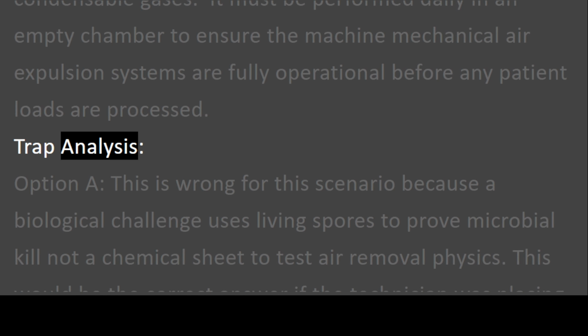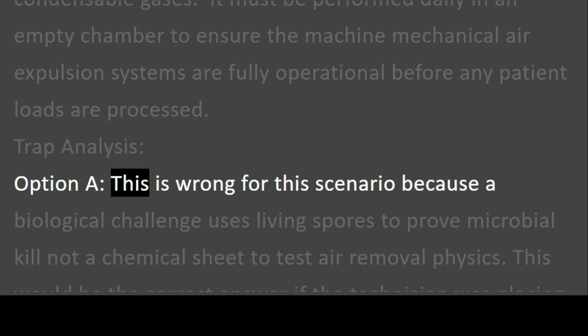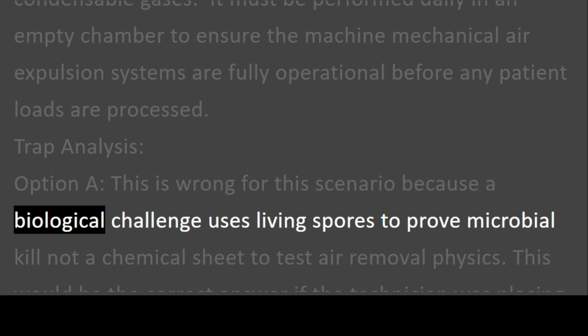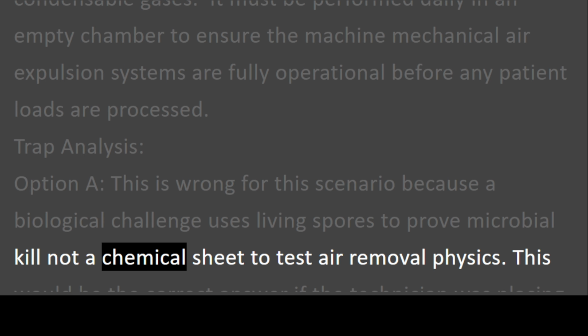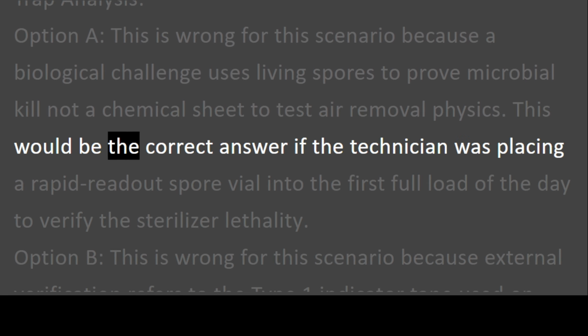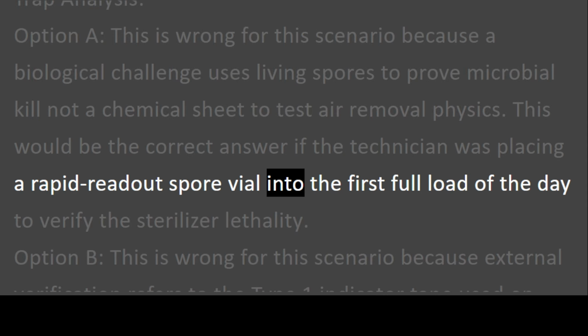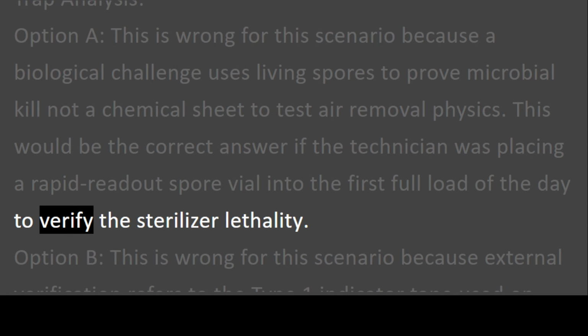Trap analysis. Option A. This is wrong for this scenario because a biological challenge uses living spores to prove microbial kill, not a chemical sheet to test air removal physics. This would be the correct answer if the technician was placing a rapid readout spore vial into the first full load of the day to verify the sterilizer's lethality.